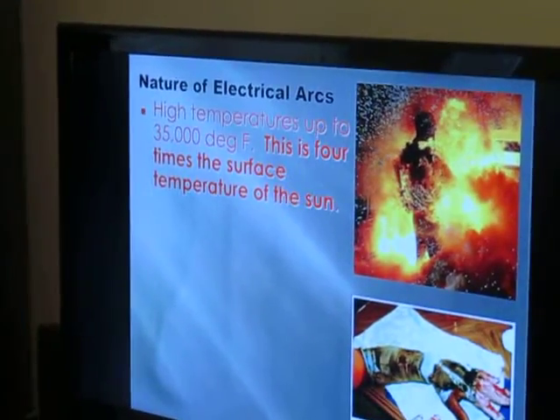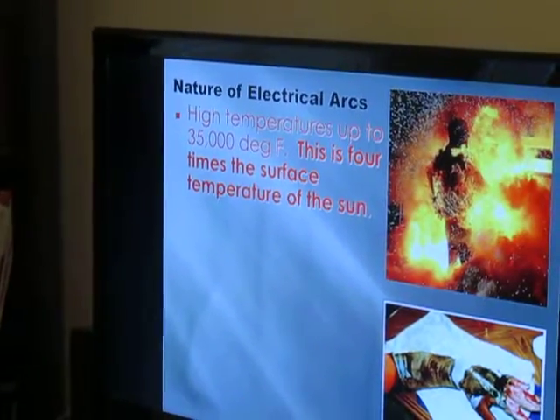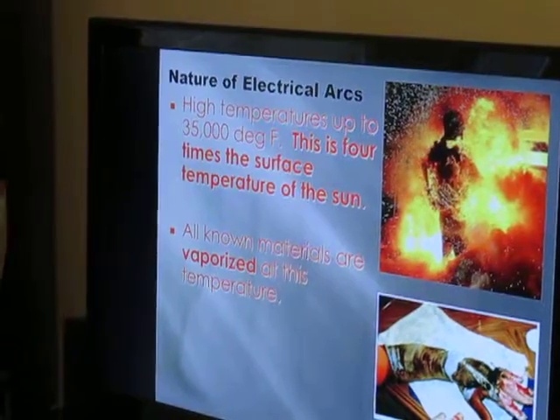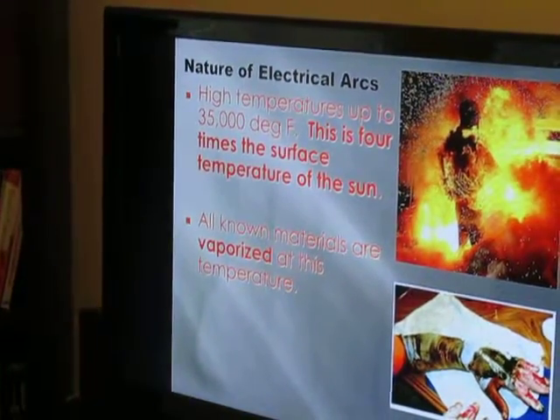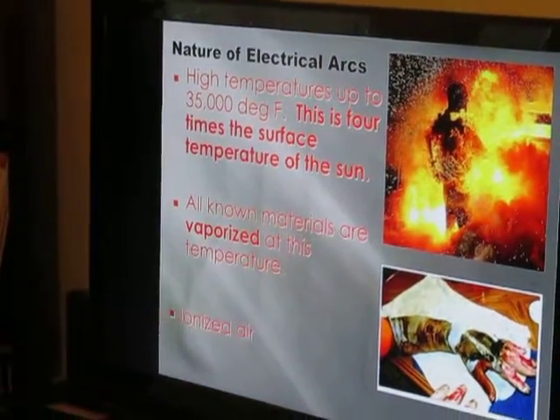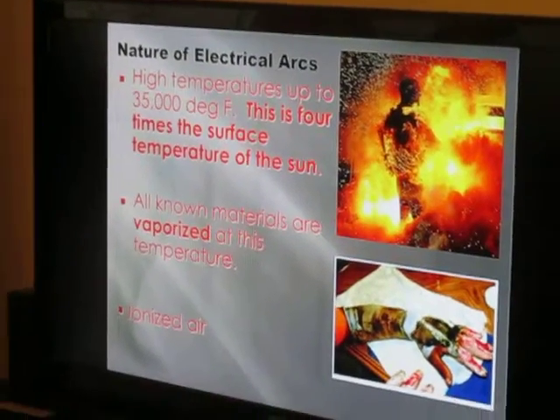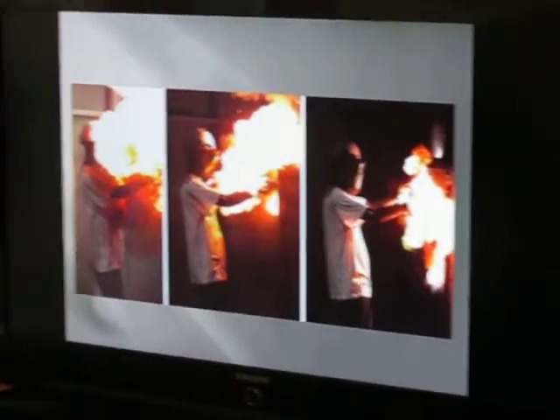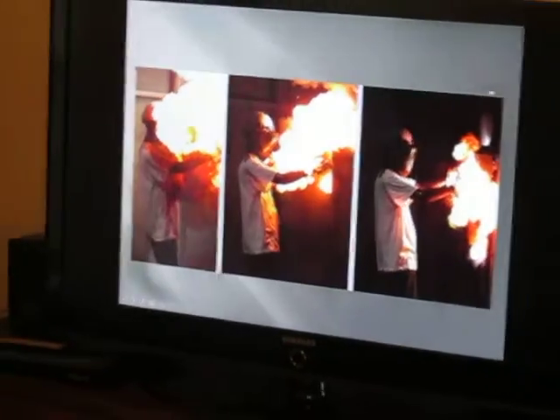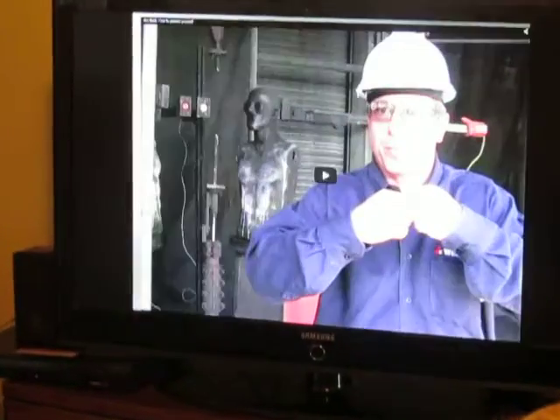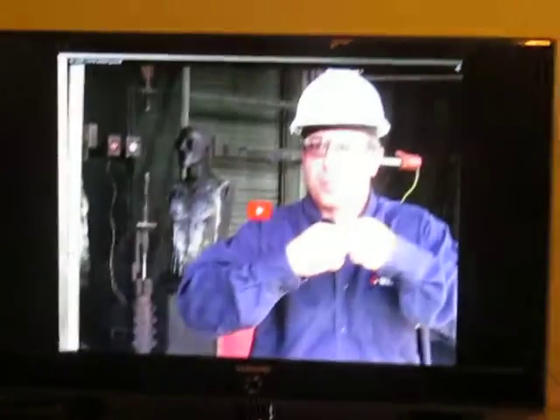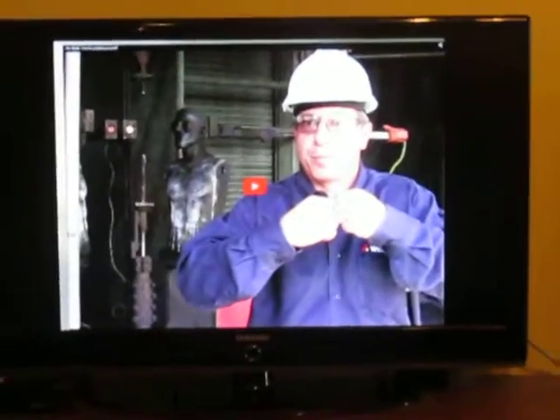The nature of electrical arcs. It has very high temperature, up to 35,000 degrees. It's 4 times the surface of the sun. All known materials will vaporize at that temperature, and it will also ionize the air. There's a photo of an arc flash. We've got a short video of it.